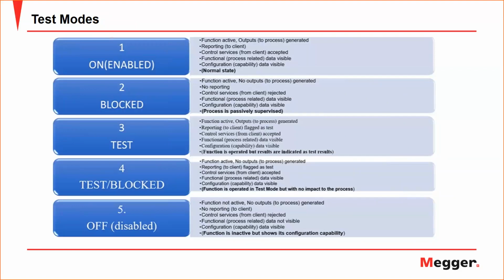The second stage we have is blocked, which means that the function is active, it is on, it is processing the input coming to it, but it's not outputting any contact or any outputs to, for example, breakers or switches. Then we come to the test mode. In test mode, the function or logical node is active and processing inputs, but only inputs that are flagged as test, or even, in the new editions, called simulation mode. It will only process values that come with a simulation flag. So anything that is injected by test equipment will be processed in the test mode.